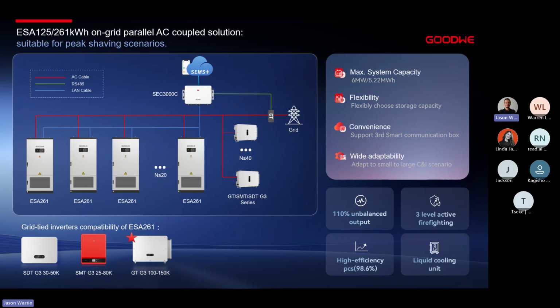Next, and lastly, the ESA 125 261 kilowatt hour. So this is our PCS. It is a 125 kilowatt PCS with 260 kilowatt hour battery that is all in the cabinet. This has got multi-stage level liquid cooling and fire suppression. It has got an air conditioning unit built into it to make sure that everything remains cool and temperature controlled, obviously through the liquid cooling.